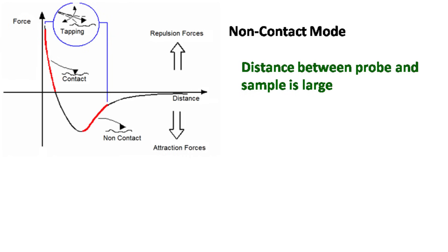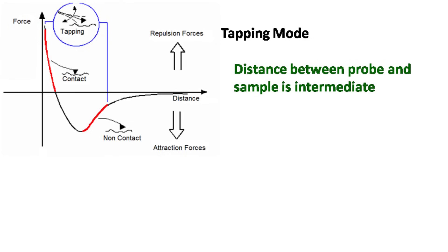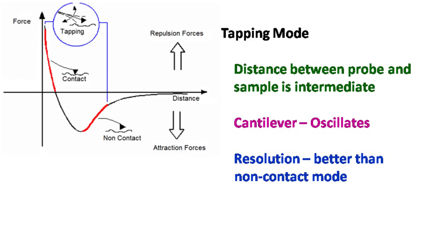In non-contact mode, the distance between the probe and the sample is kept large. As a result, the cantilever is attracted. The resolution obtained is low, however the sample is not damaged. In tapping mode, the distance between the probe and the sample is kept intermediate. As a result, the cantilever oscillates and the resolution obtained is better than in non-contact mode.